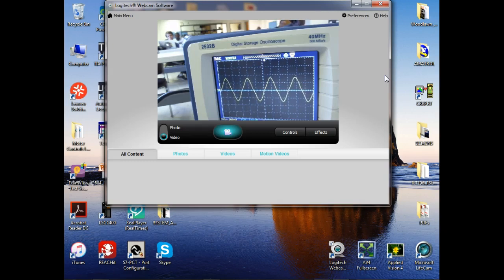They last a lot longer, right? And if I needed DC, I would just put a rectifier circuit on this and turn it into DC for my control circuit. Pretty neat, but if I took this and converted it to digital by using a transistor, what we call a saturated switch, we can convert it into digital very easily, and I could take it directly into a PLC, to a high-speed counter, and count it and do the math. So now I can figure out the RPM of the motor because now we have a frequency.